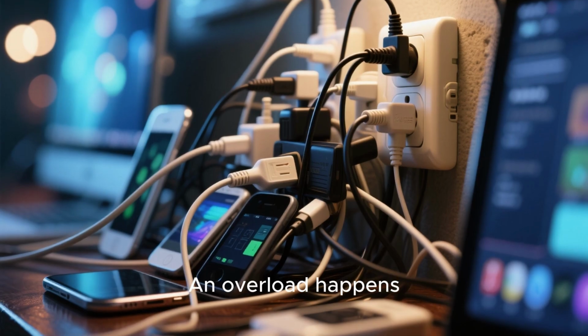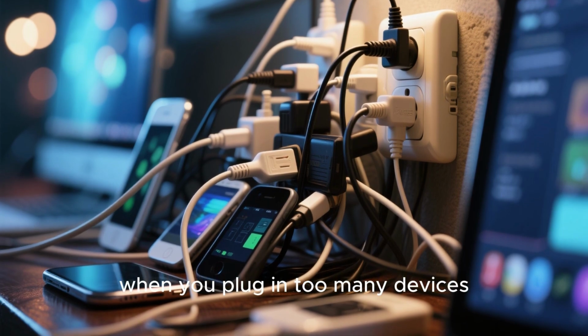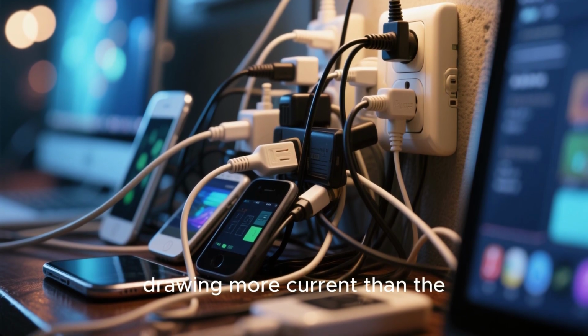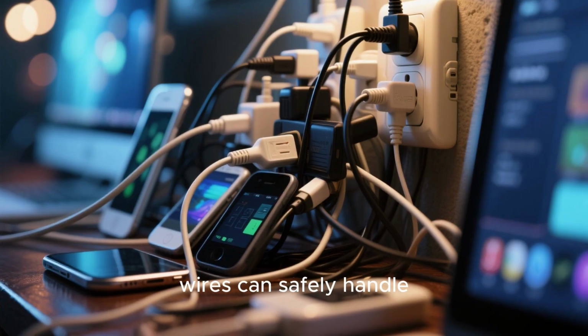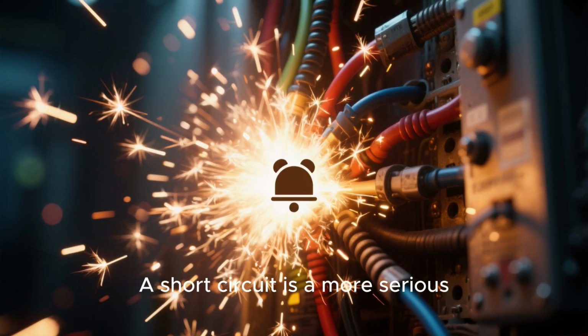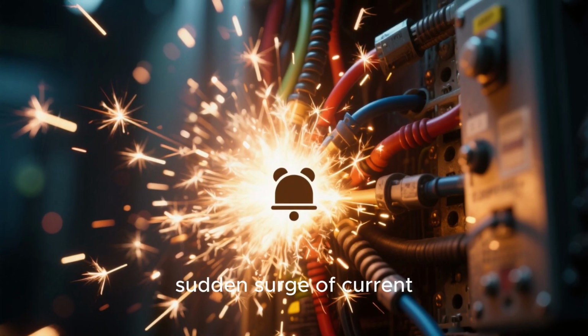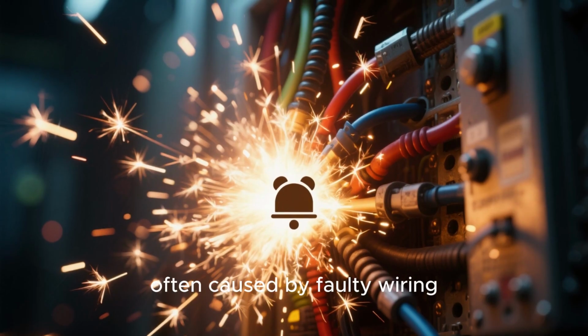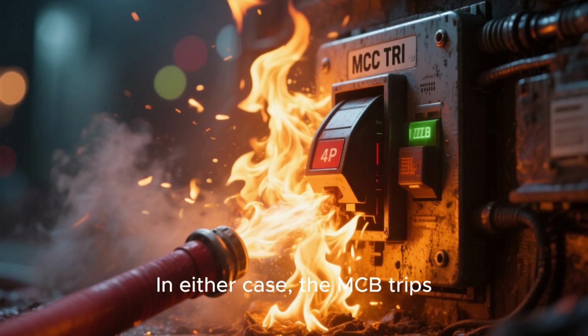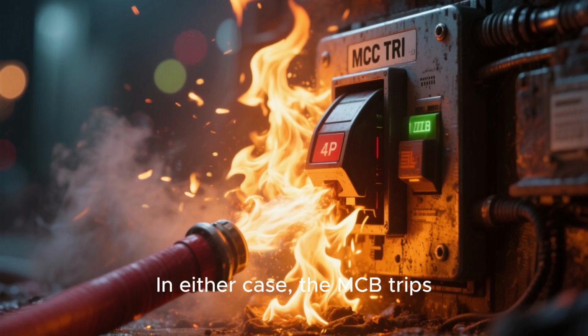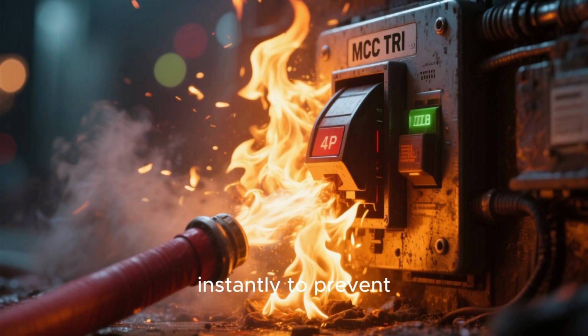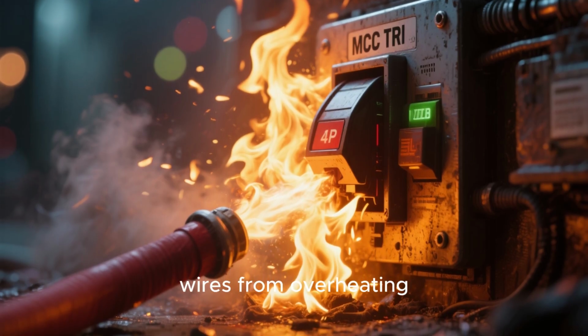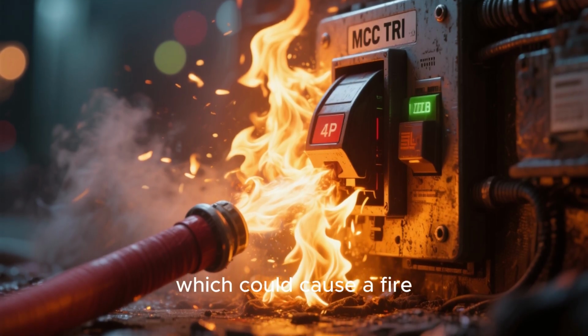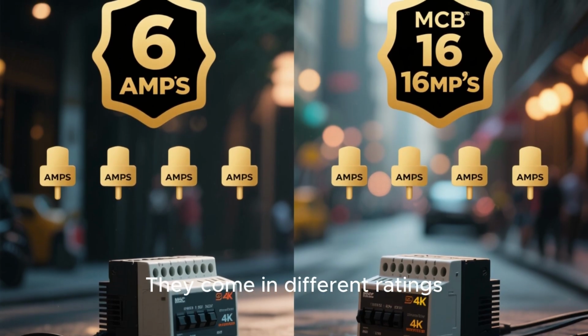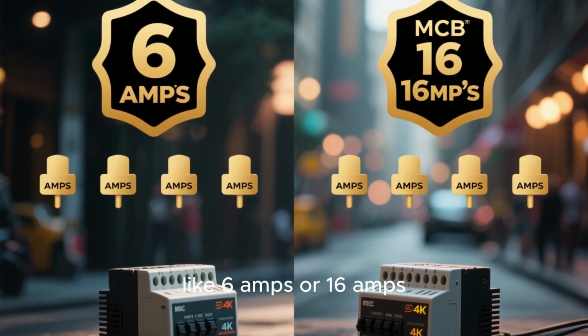An overload happens when you plug in too many devices into one circuit, drawing more current than the wires can safely handle. A short circuit is a more serious, sudden surge of current, often caused by faulty wiring. In either case, the MCB trips, cutting off the power instantly to prevent wires from overheating, which could cause a fire. They come in different ratings, like 6 amps or 16 amps, matched to the circuit they're protecting.